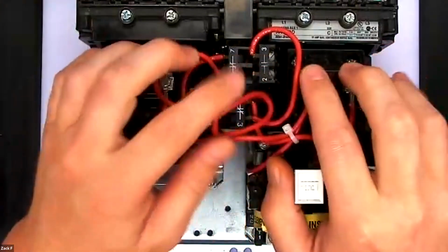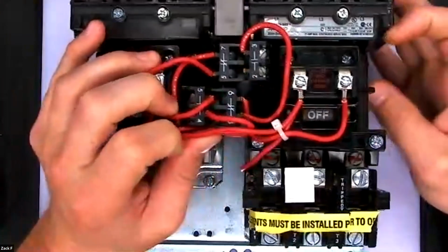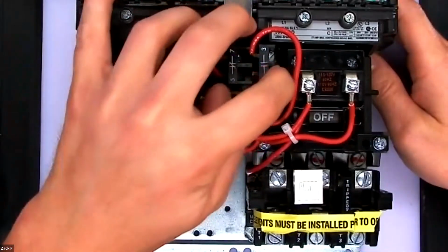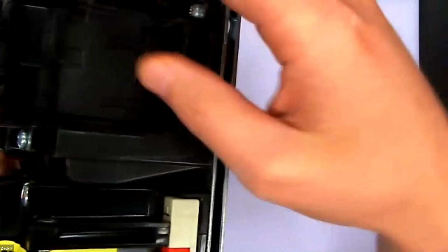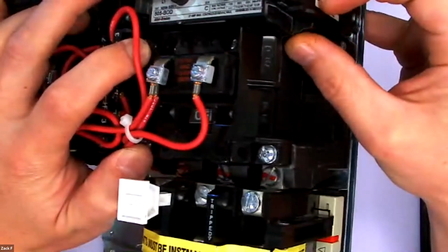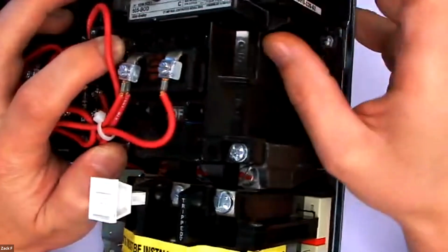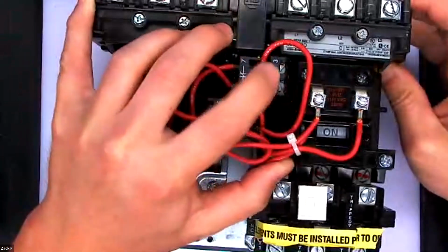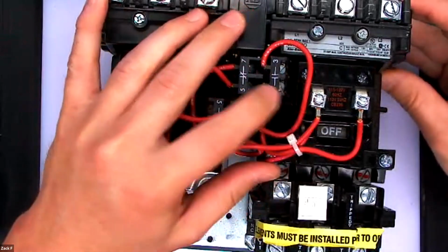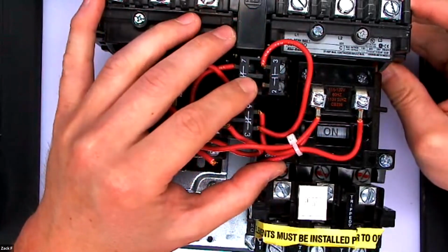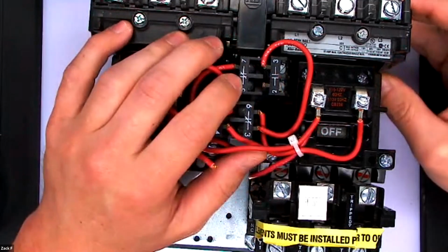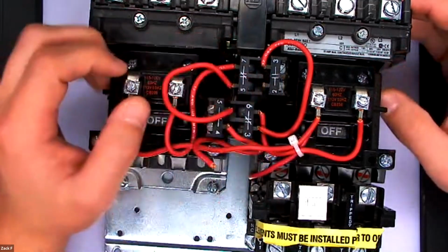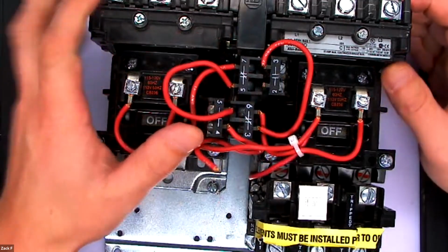So if I change the state of this coil, how these work is there's a little tab. I'll show you some that aren't hooked up, but inside here where you can't see it, there's a tab that changes the state when that coil pulls in. This little doohickey on the side pulls that tab up and changes the state of the contact. So when the coil energizes, this becomes closed and this opens up. You could have all sorts of uses. You can use them for holding contacts. You can turn a light on whenever the motor's on, whatever you want to do. That's why they're called auxiliary. 10-4? Good, buddy.